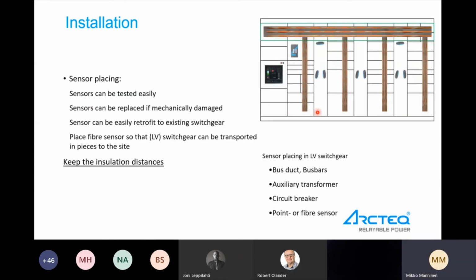Typical sensor placing for the low voltage. This is done with the point sensors. This is a very common way to do it if we have horizontal bus bars and vertical bus bars, where we have this master unit, or the relay itself, here. And then we have point sensors. This one is the cable compartment. And this point sensor is looking left to the vertical bus bars. This one is looking right to the vertical bars, and this one is looking to the bus bar section.